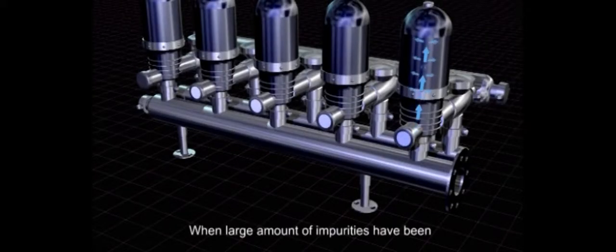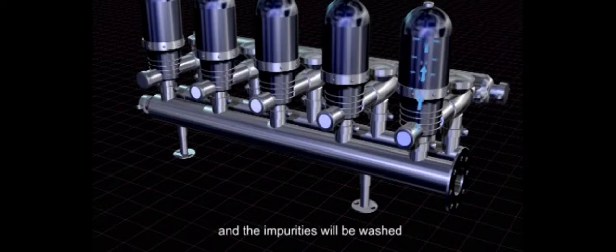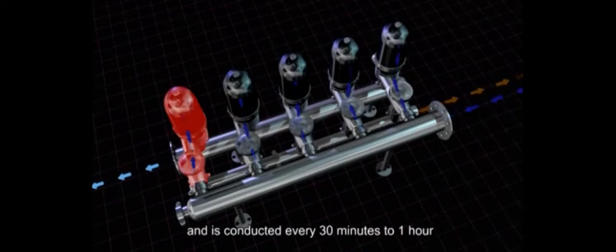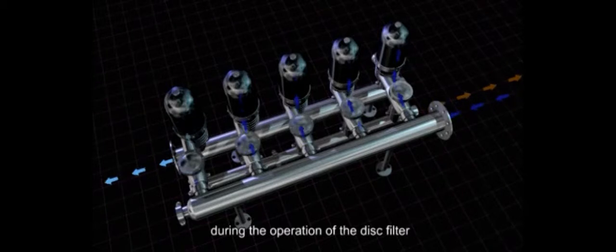When large amounts of impurities have been accumulated on the filtration element, the water flow direction will be changed and the impurities will be washed away by the filtrate. This process is called backwash and is conducted every 30 minutes to 1 hour during the operation of the disc filter.